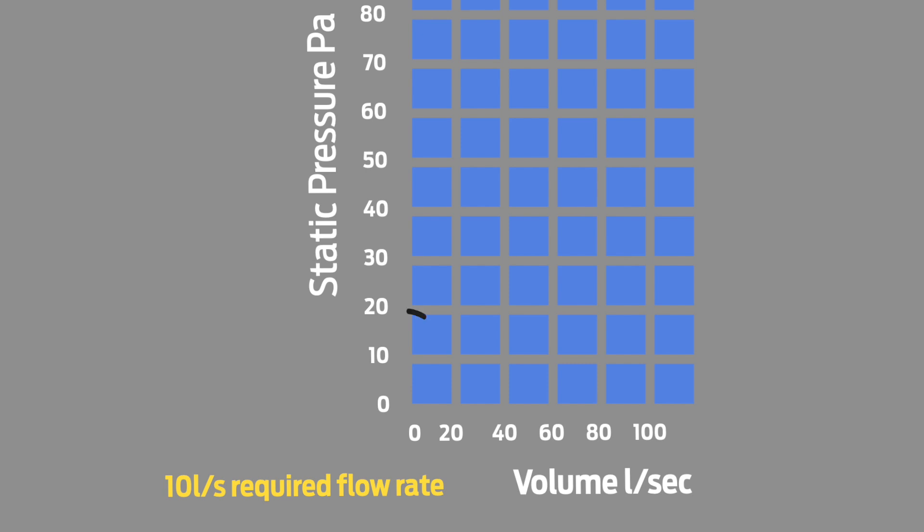Let's look at the 100mm fan first. Assuming we have 8 metres of straight duct, this would mean around 16 Pa of pressure drop over its length. As you can see, this sits inside the curve, so we can hit our target flow, ignoring bends and grills at this stage.